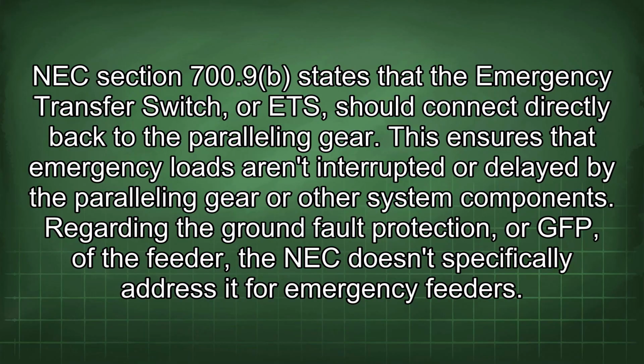NEC section 700.9(b) states that the emergency transfer switch, or ETS, should connect directly back to the paralleling gear. This ensures that emergency loads aren't interrupted or delayed by the paralleling gear or other system components.